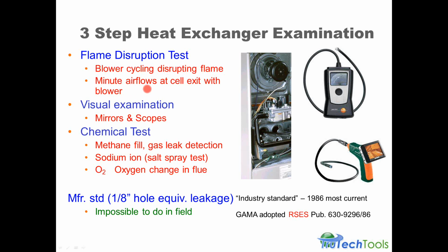You can also look for minute airflows at the heat exchanger cell exit with the combustion turned off, but with the blower cycling on. Sometimes we've used a hot wire anemometer to actually look for small airflows at the heat exchanger cell exit, and this would be on an atmospherically vented system. There's also visual examinations that can be done with various mirrors and visual inspection scopes to actually get inside and take a look at the integrity of the heat exchanger itself.